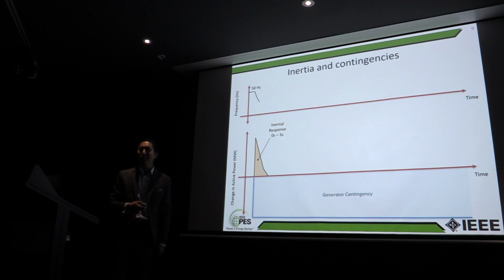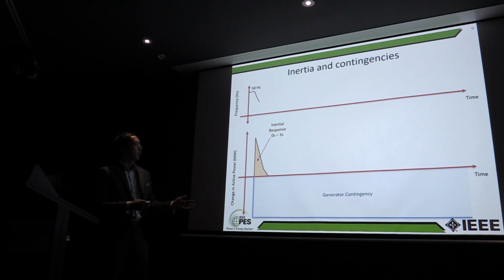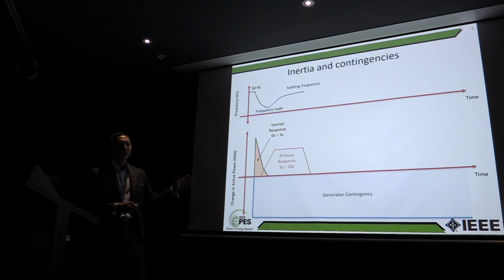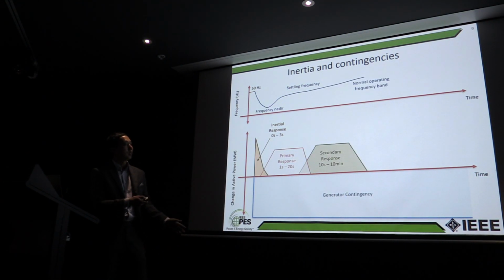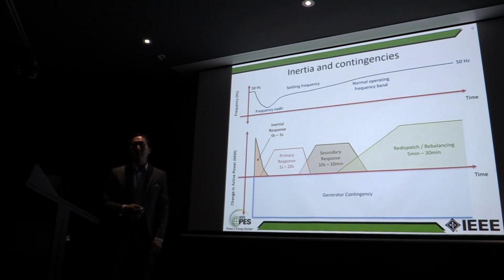Now, if we just had inertia, what would happen? Frequency would go to zero, you would just have a blackout, because you would run out of energy from the rotating masses. They'd slow to a standstill, and then we get nothing. So what we actually need is something called primary response. This is all other generating units starting to ramp up their power. In the first 20-odd seconds, that settles the frequency to a frequency nadir. Sometimes it's called containment reserves, frequency containment, and that settles out at some frequency. This frequency is not 50 hertz, as you can see. What you need then is something called secondary reserves, which brings it back to the normal operating band, the 49.8 hertz. And then after that, you have really normal operation.